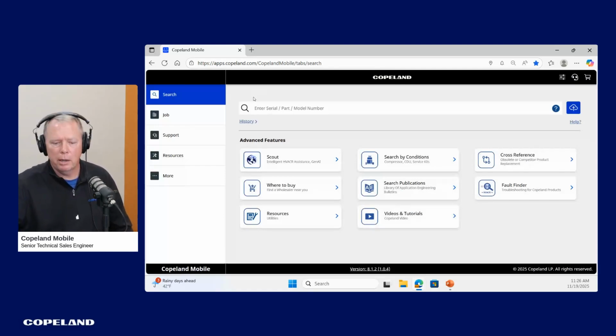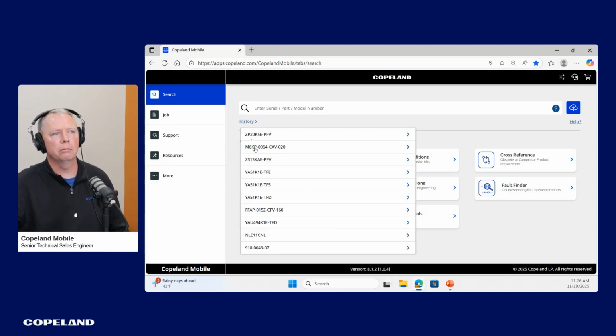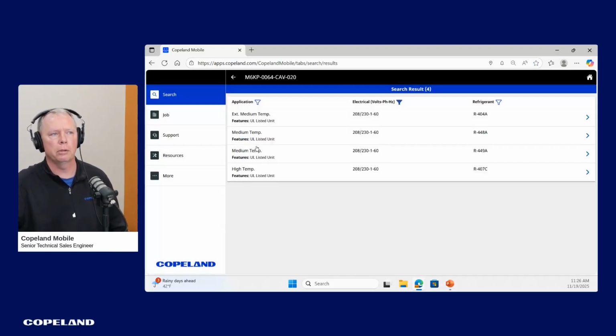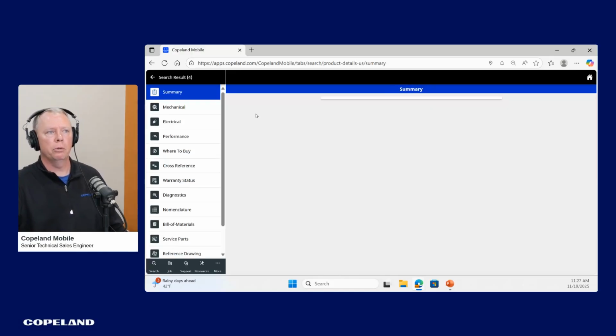So one of the things I wanted to talk about was condensing units. Absolutely, one of the items we discuss quite a bit is Copeland condensing units. For this example, I'm going to use an M6 KP, a smaller Copeland condensing unit. One thing to be aware of is that the majority of Copeland units do not come pre-charged. They usually have a nitrogen charge because applications and line lengths vary, and as you can see, this is a multi-refrigerant unit, so it would be very difficult to pre-charge. However, a question that does come up is, what is the charge amount for this unit? Well, you don't always know, because there are a lot of variables.